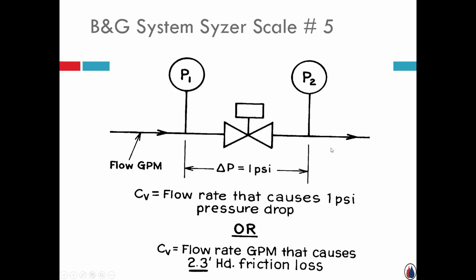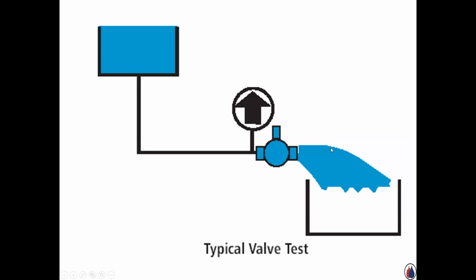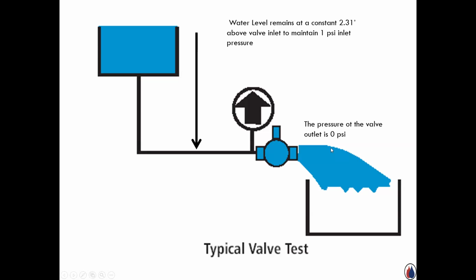Okay, yeah. And really what it is, the manufacturer is testing. And what happens, I guess, again, next picture, how they test the valves. Water level remains constant right here on the left-hand side at 2.3 feet, maintaining that 1 pound inlet pressure. Pressure at the valve outlet is 0. It's dropping into a container that's going to measure that amount of water. The volume of water flowing for 1 minute can be weighed to determine the gallons per minute. That becomes, whether it's Honeywell, Siemens, Johnson, Powell, any of the valve manufacturers, they all have a C sub V rating. They test the flow through an orifice to say, I know this valve's capacity.